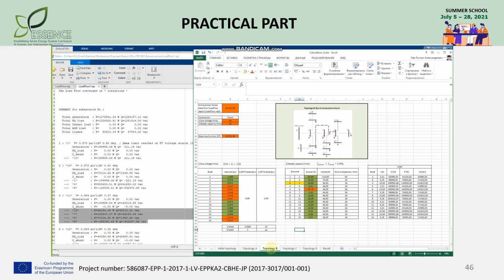Now we need to do the same for the rest of the 3 topologies. In the case of the topology where bus 6 is tied with bus 4, the voltage of 7 buses is lower than accepted boundaries, and the branch to 6 is overloaded. So the constraints are not met. Moreover, since the currents are increased, the losses are also much higher than in the initial case.